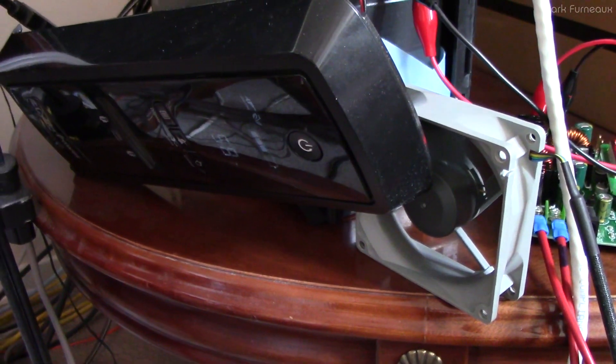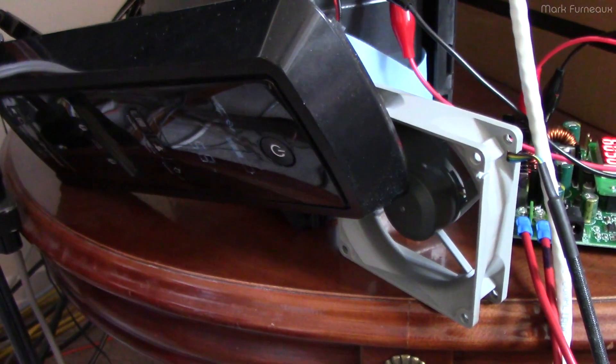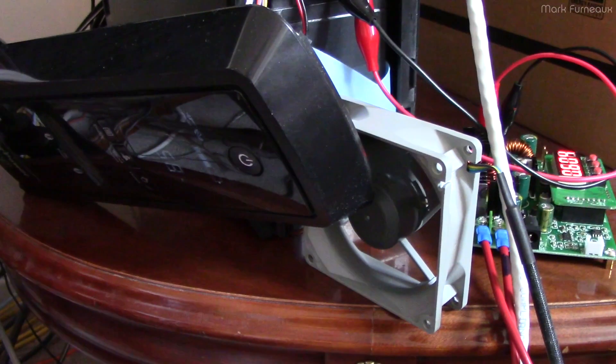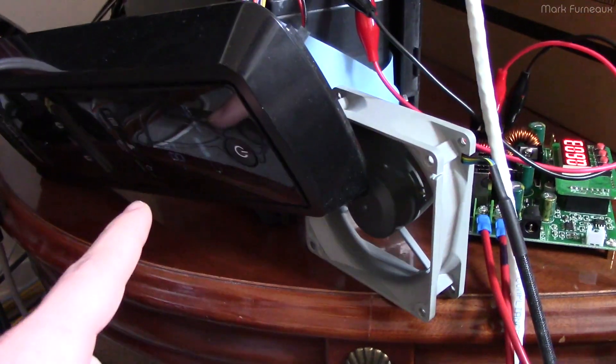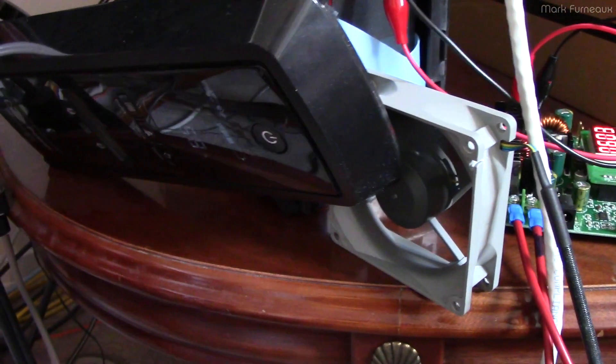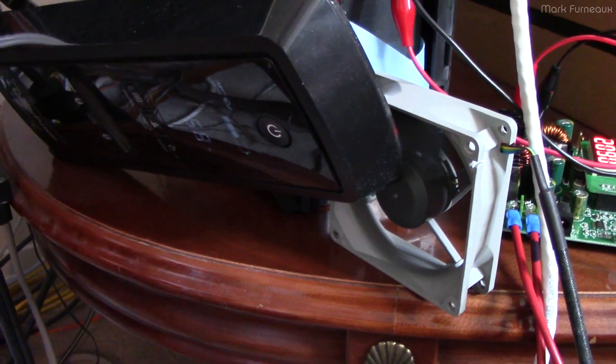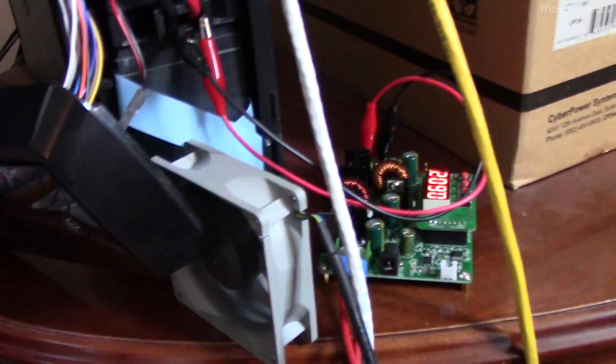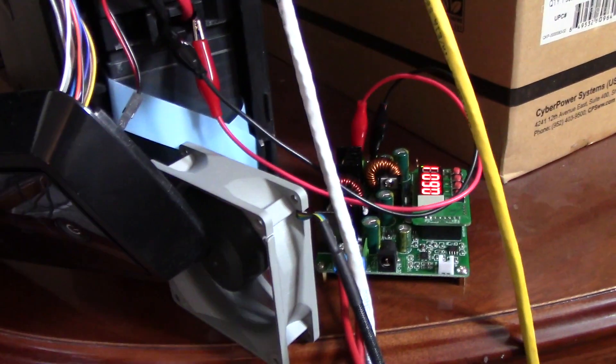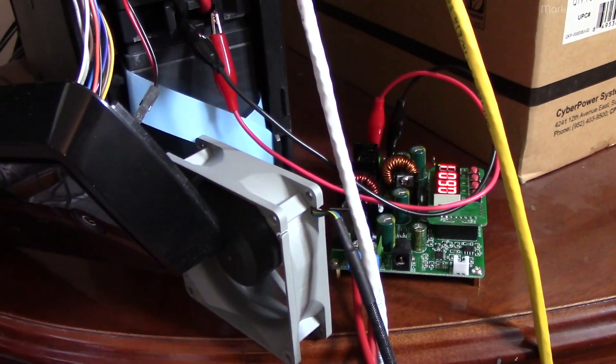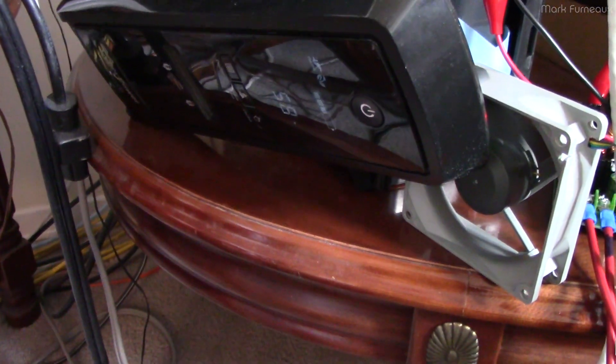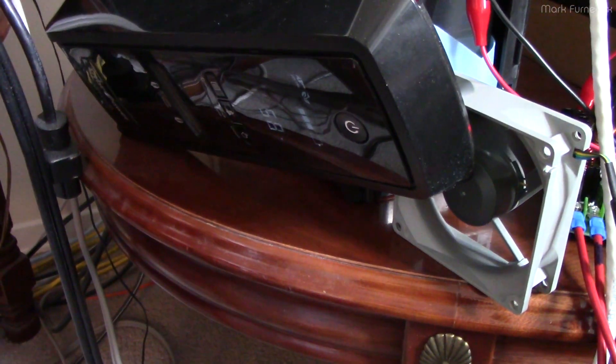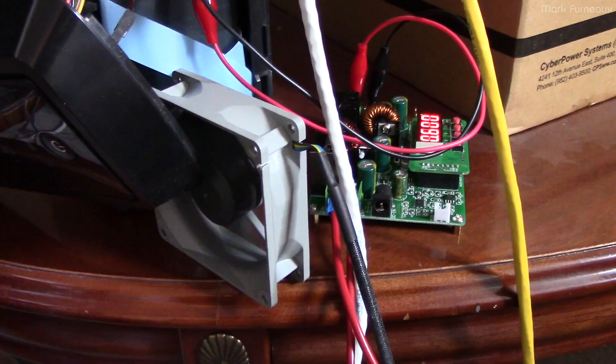And so when this reaches 100, if you have a UPS with a relatively discharged battery, it could say 100 and it not be even close to 100. Or, in my case, the battery is already approaching 100%, and yet it still says it's 50-something percent, which is not correct, not even close. In fact, this battery would technically be 100% as it is now. I'm just doing the equalization charge on it.